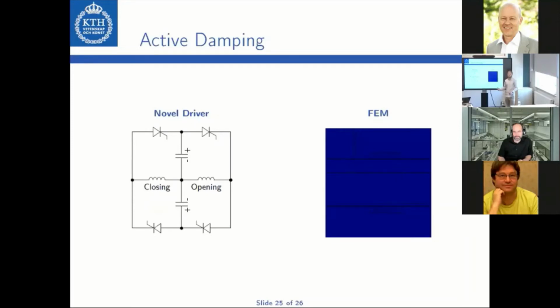The other aspect is this proactive commutation mode. Here you operate the actuator twice within 10 milliseconds, so it is really questionable how to recharge a capacitor within this time frame. That's why this driver has a lot of potential for this kind of application, where recharging within a short time would not be feasible with a practical implementation of the DC power supply. You would have to have several supplies or several capacitors for that. With this one, the recharging is automatically finished after the action.